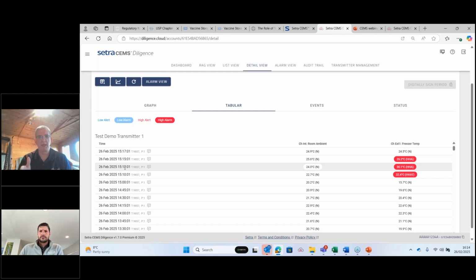In the background it's checking every minute what you've programmed, and if it sees a breach of your alarm limit level, it will automatically wake up, establish a Wi-Fi connection, and send the alarm notification to whoever's going to receive it. It will also show locally on the display that channel 1 has gone into high alarm, beep about 10 times, and flash a red LED that continues until you acknowledge the alarm, while the display also shows high or low alarm status.